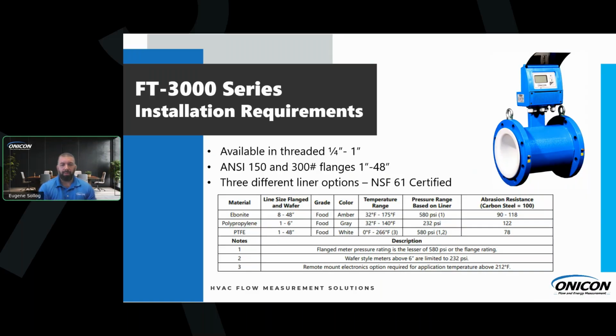We also have 3 different liner options with this. All of them are NSF 61 certified. We have ebonite, polypropylene, and PTFE. Ebonite and polypropylene are typically what we're going to be seeing for your chilled water, domestic water, condenser water, just regular water with mild additives, like any kind of glycol. It doesn't really care about that. But the cooler temperatures apply: for ebonite below 175, and for polypropylene below 140.